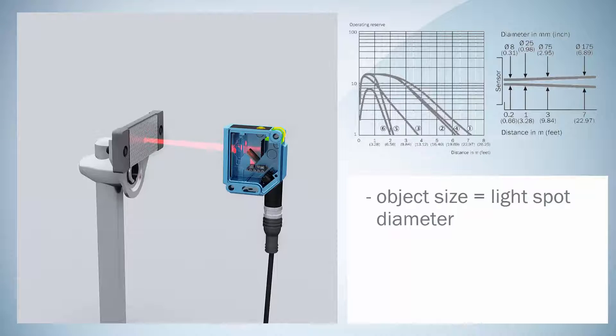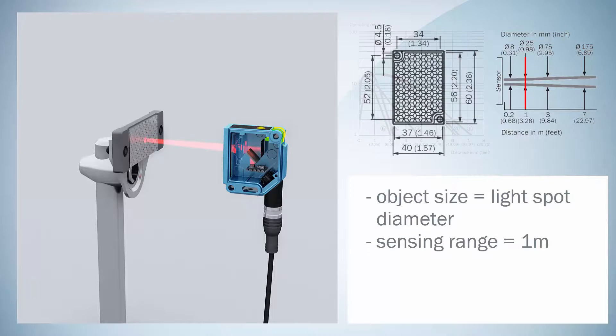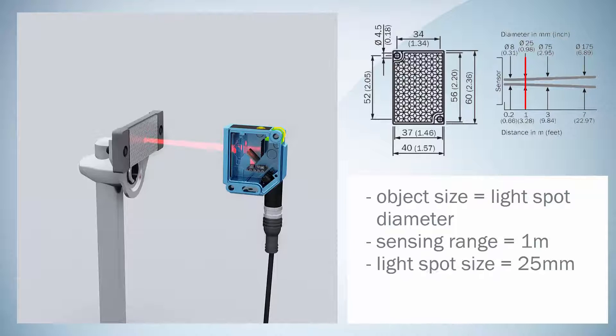In our demonstration we'd like to cover a sensing range of 1 meter and use a PL48 reflector. This reflector is used due to the fact that the datasheet shows that the light spot diameter at 1 meter is 25mm and the reflector should be of a similar size. The PL48 dimensions of 56mm by 40mm fit perfectly.